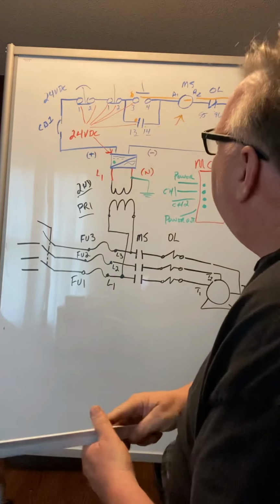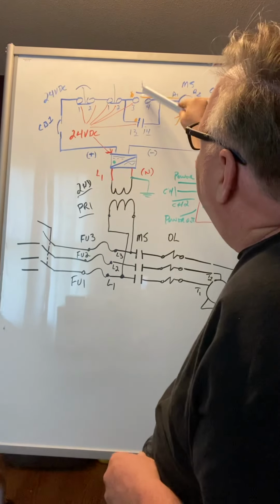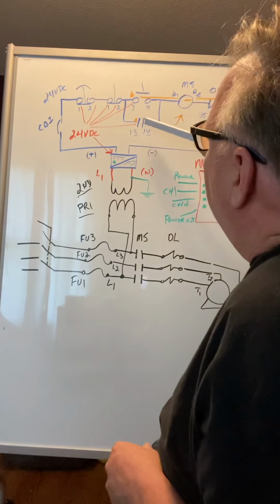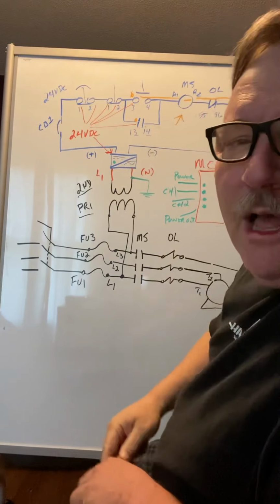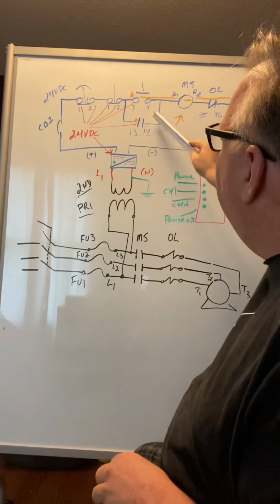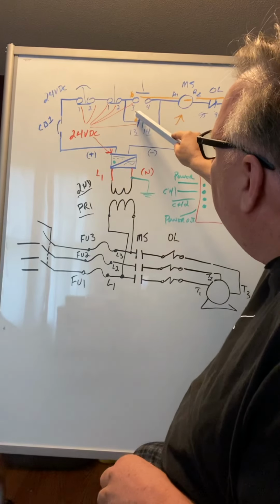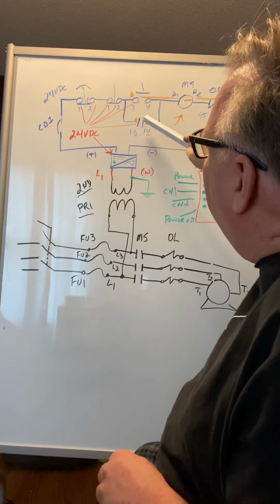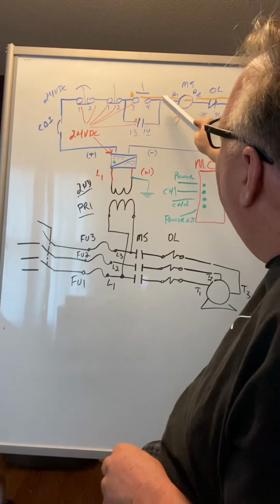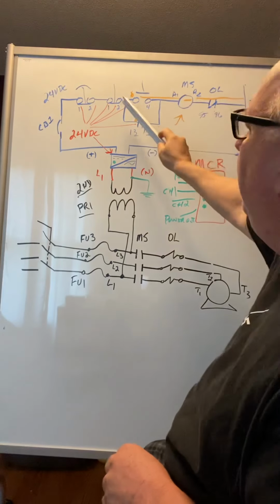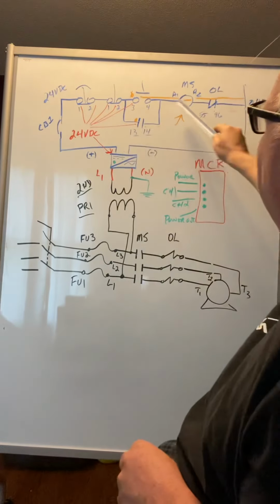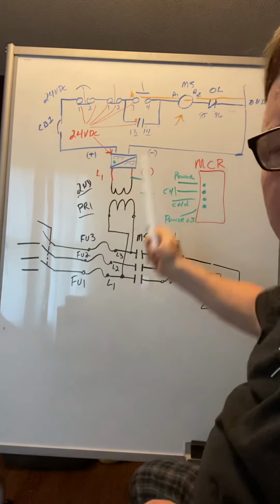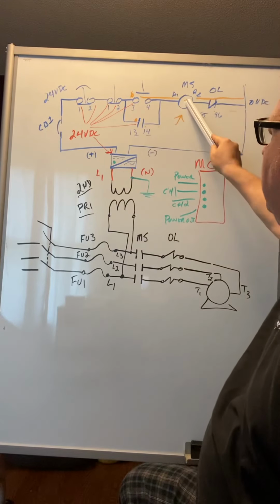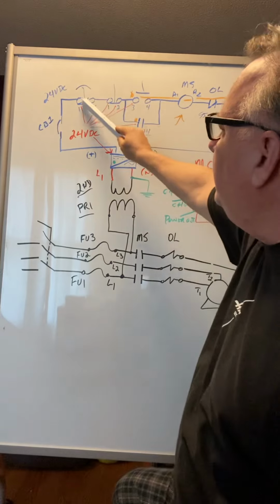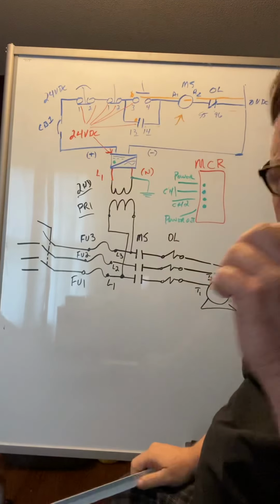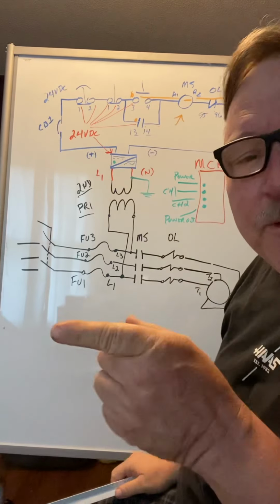The next typical presentation is the operator says, I can push this button and the machine comes on, but when I release the button, it stops, okay? Now we have the opposite. Now we need to start looking at it. Remember where I have these red lines, you should have 24 volts. If you press the button and the machine comes on, there is nothing wrong with the circuit going straight across. The overload is okay, the armature is okay, and all of these push button switches are okay. If it wasn't, it wouldn't come on with the push button.